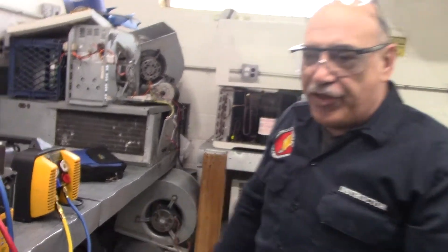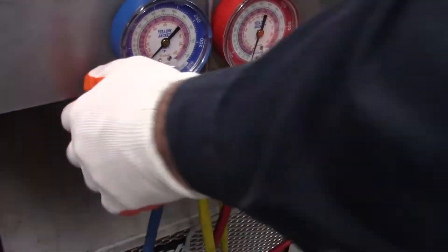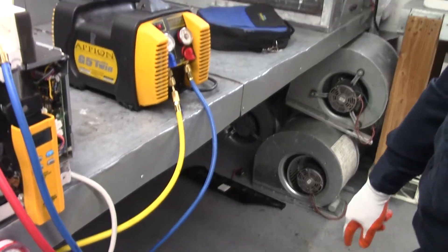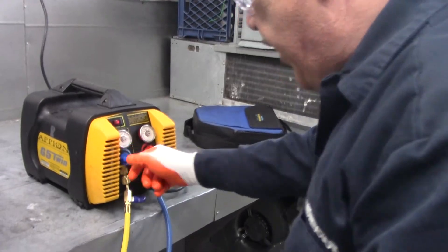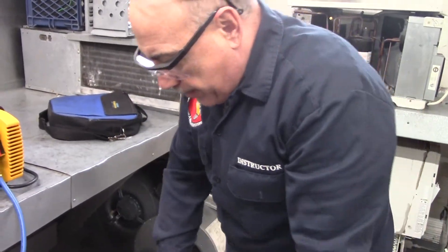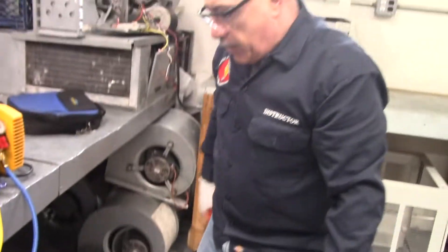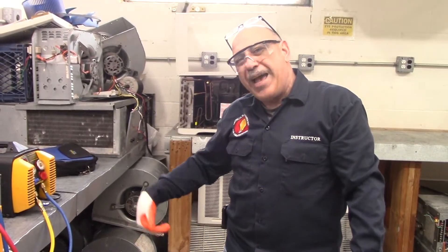Now we are down to zero on our gauge, so we are going to treat this as if it had a leak in it. We are going to shut our gauges here, let the pump continue to pull into our tank, and shut off our hose. Let whatever is in the pump continue to pump into the can. Then we are going to close the can and shut off our unit. That will hopefully, with the Appion, get as much refrigerant back into the can.